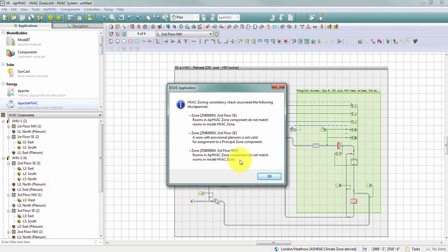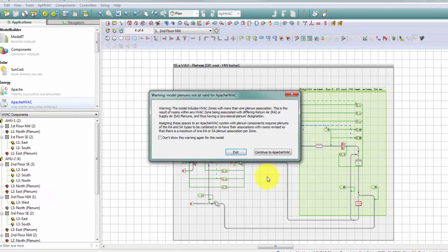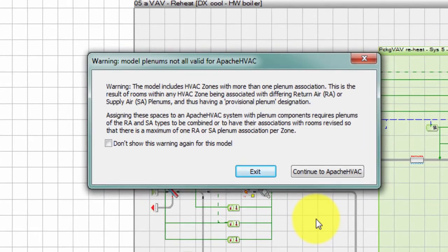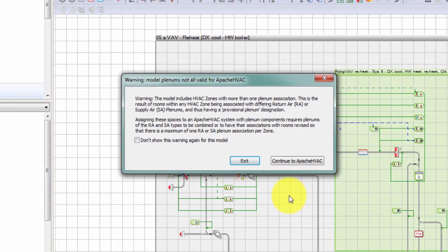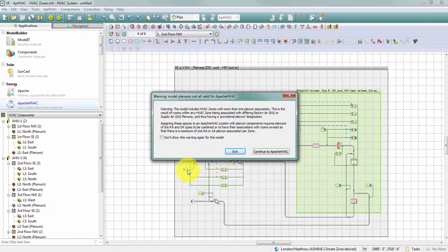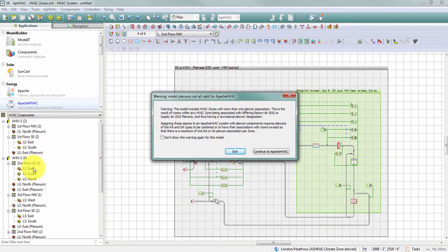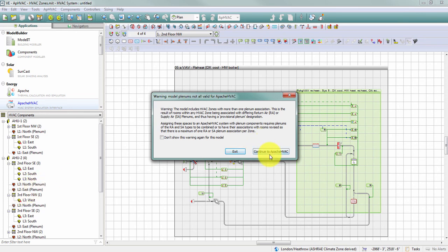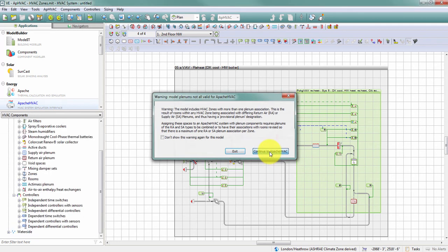The third is noting that another one of my zones now has fewer spaces than previously. So again, the spaces assigned to the zone in the HVAC network do not match the spaces assigned to the zone in the model. This next warning message is letting me know that my model includes HVAC zones with more than one plenum association. So that's talking about this second floor southeast zone that now has two return air plenums associated with it. I am allowed to continue to Apache HVAC and keep working, but I will need to correct this at some point prior to running my simulation.